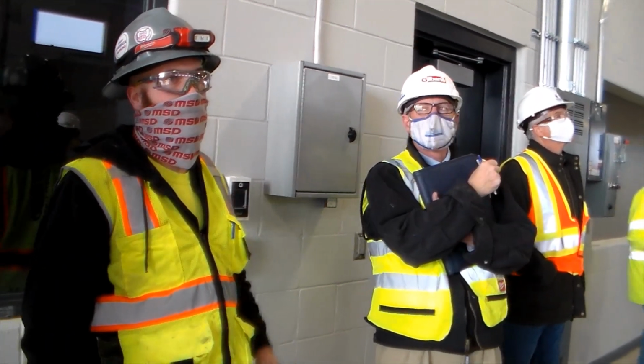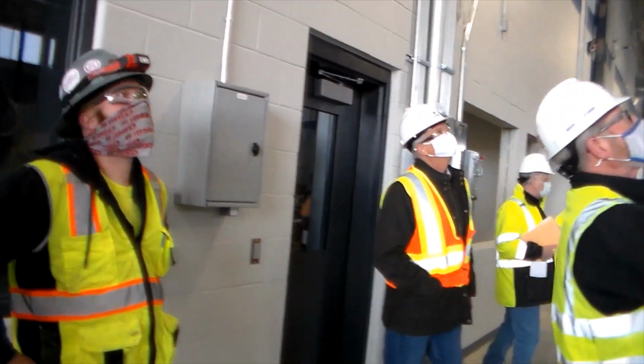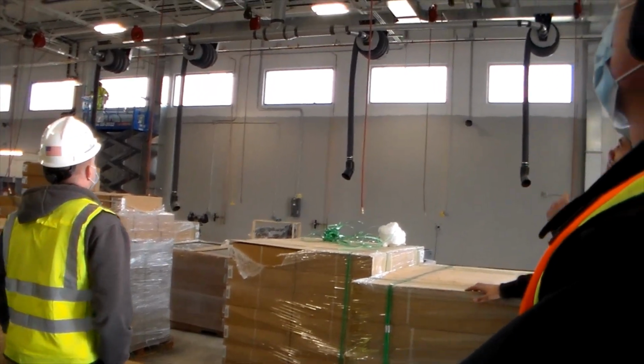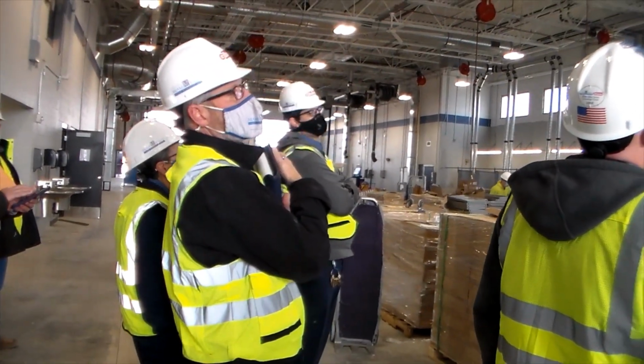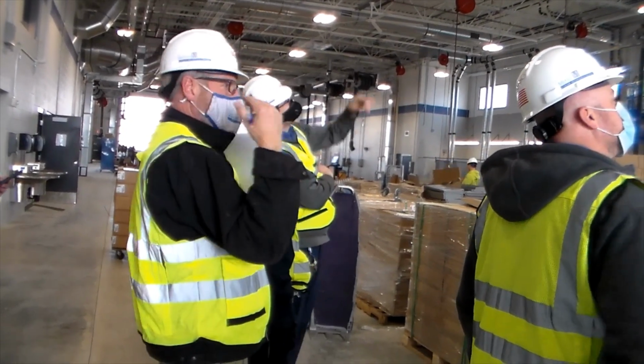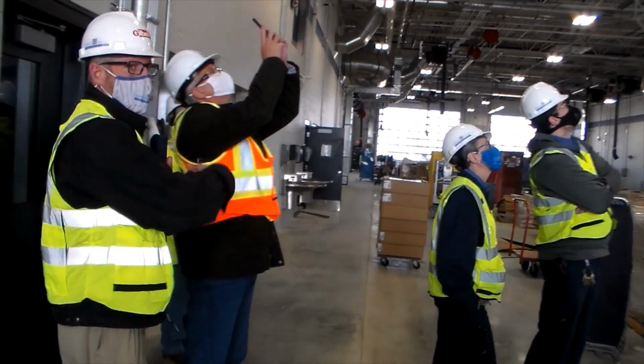Josh? These guys, they have a monitoring module. You can see up in the ceiling here, just above, there's a relay that turns all the fans off with the fire alarm. So that red box right there? Yeah. Is there anything resettable in that box? No. So it just goes off when the alarm system clears? Yes. Got it.